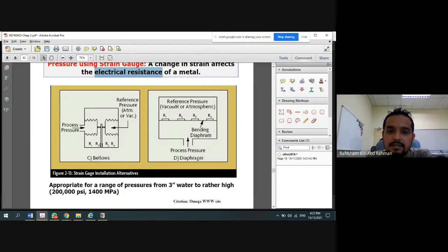If you look carefully, the pressure reference at this point is vacuum or atmospheric conditions. And then we have a pressure here. Let's say this one is a tank, a gas tank. This one is connected to the gauge, and this tank will push the diaphragm. Diaphragm is a film. You have one layer. The pressure will push the layer. The layer will change the resistance of this one, and then that will reflect to the values.